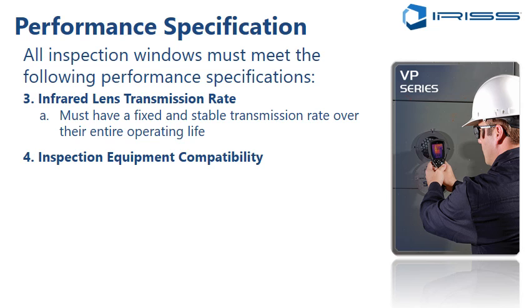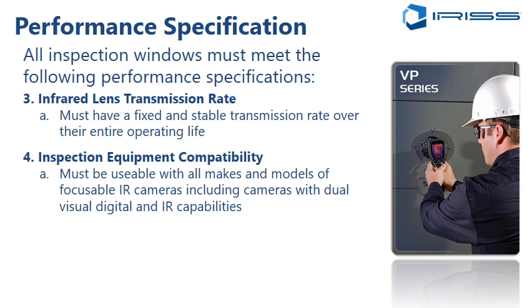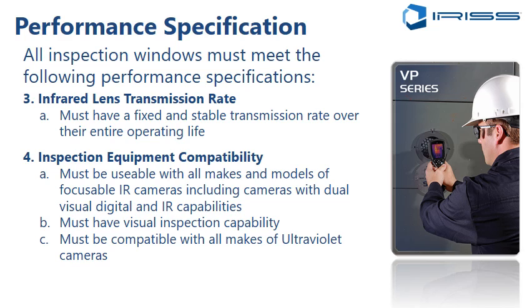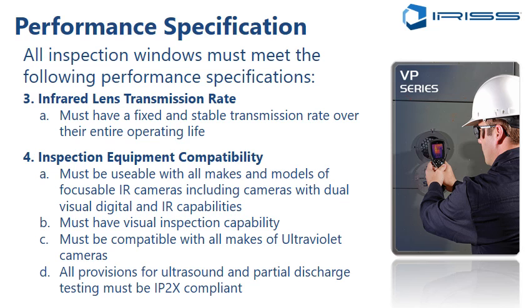Inspection equipment capability: they must be usable with all makes and models of focusable infrared cameras, including cameras with dual visual, digital and infrared capabilities. They must have visual inspection capability and must be compatible with all makes of ultraviolet cameras. And all provisions for ultrasound and partial discharge testing must be IP2X compliant. So if you're going to build ultrasound ports or partial discharge ports into your maintenance inspection windows, they should be IP2X compliant. Okay, so these are what we class as the performance specification requirements of inspection window systems.